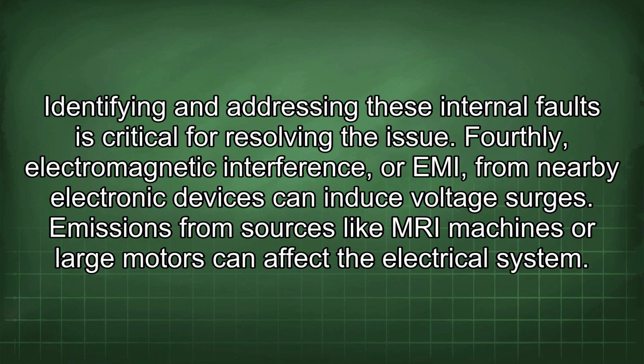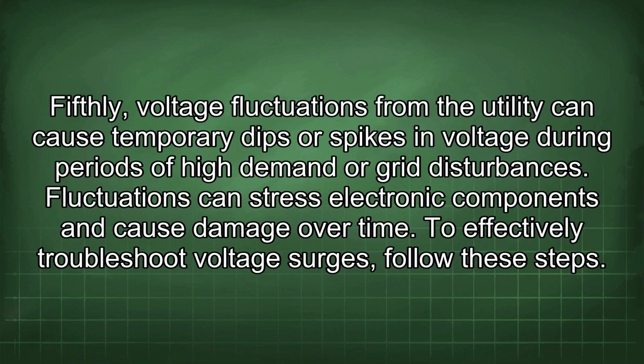Fourthly, electromagnetic interference, or EMI, from nearby electronic devices can induce voltage surges. Emissions from sources like MRI machines or large motors can affect the electrical system. Fifthly, voltage fluctuations from the utility can cause temporary dips or spikes in voltage during periods of high demand or grid disturbances. Fluctuations can stress electronic components and cause damage over time.